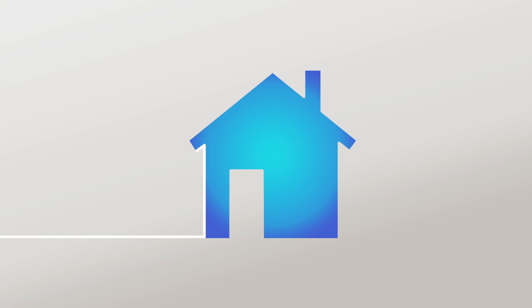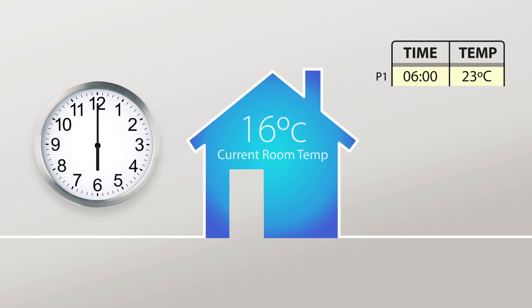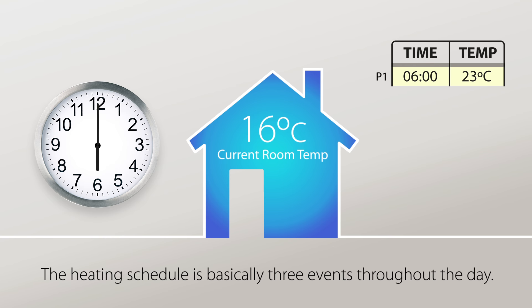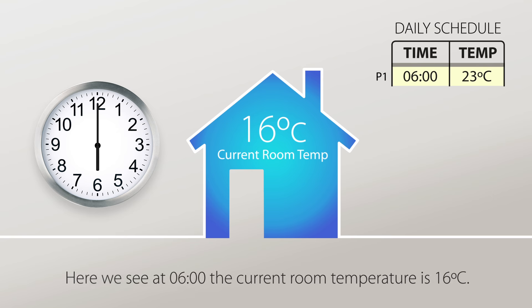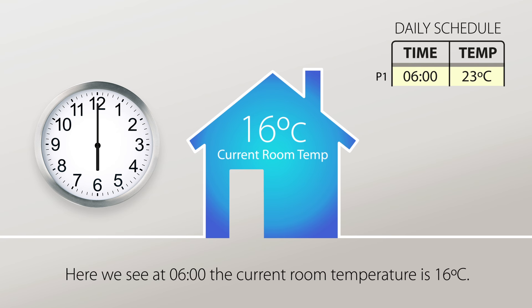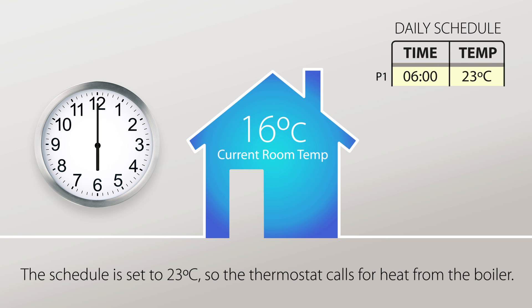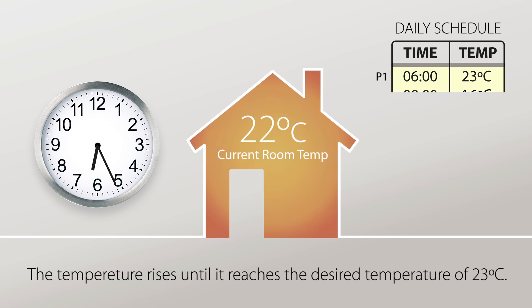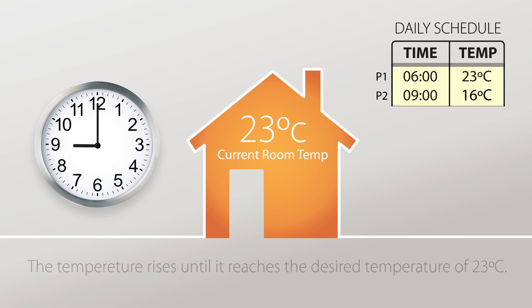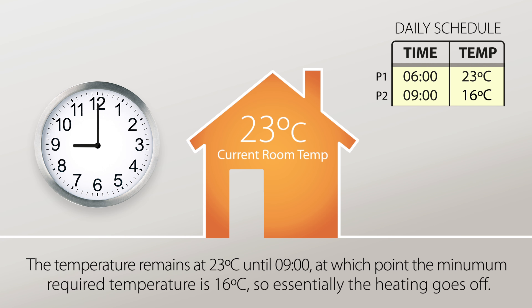This is an example of a typical heating schedule. At 6am the current room temperature is 16 degrees. Program one is the first on time and temperature — the temperature is set to 23 degrees, so the thermostat calls for heat from the boiler. The temperature rises until it reaches 23 degrees. Program two is the off time and temperature: at 9am the minimum temperature required is 16 degrees, so essentially the heating goes off.